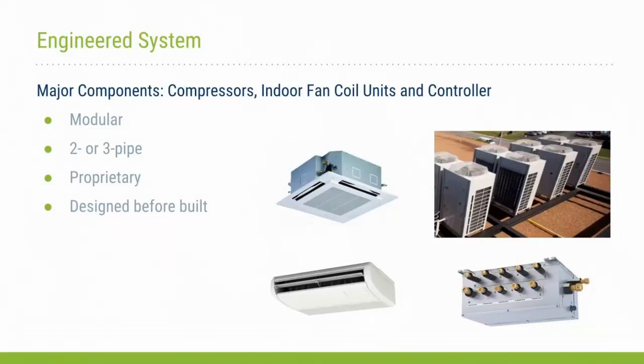System designs vary among manufacturers. Some brands of VRF systems with heat recovery require 2 refrigerant pipes, and some use 3 pipes. Systems are designed specifically for each application, incorporating appropriate components and controls. All of the components are proprietary. Each manufacturer has its own unique components, controls, and piping configuration. One manufacturer's system cannot be integrated with another's. Also, to ensure that a VRF system performs as expected, all of the professionals, from the designers to the operators who are involved in the system implementation, must have received training from the system's manufacturer. Next slide, please.